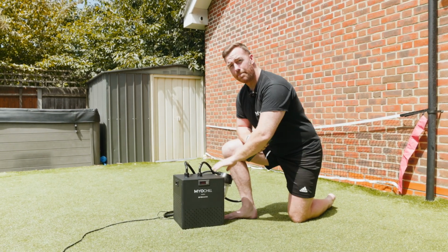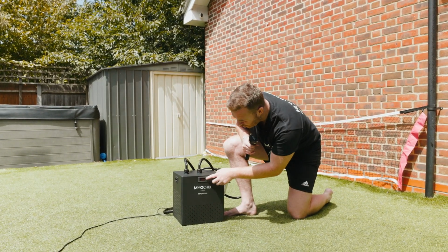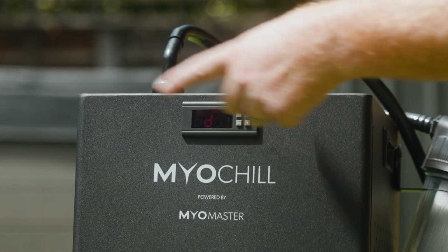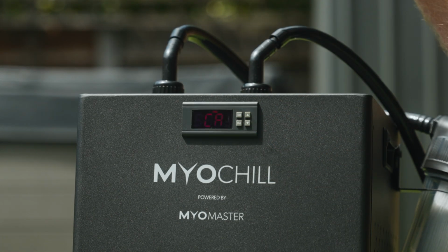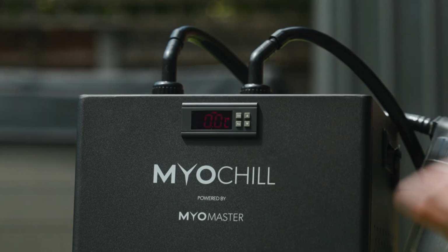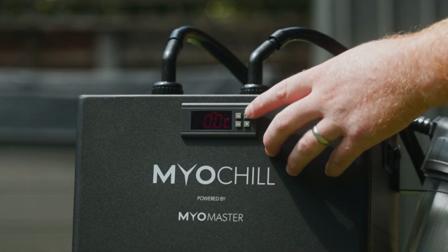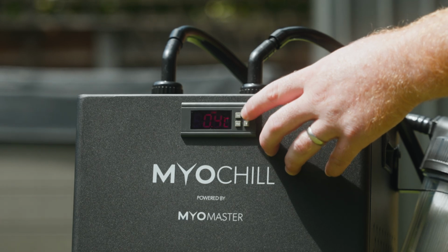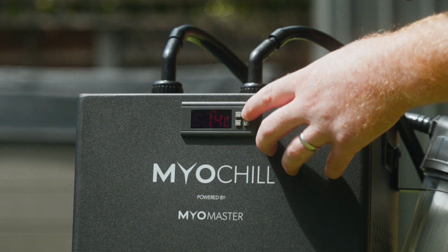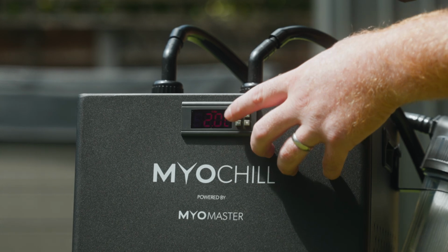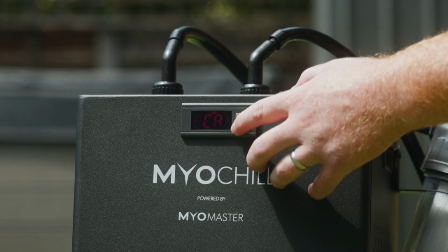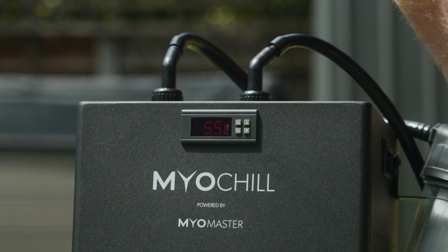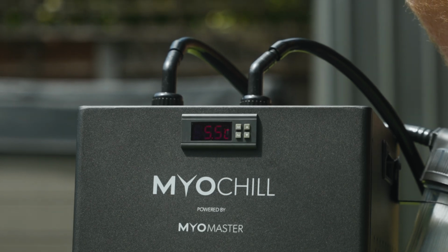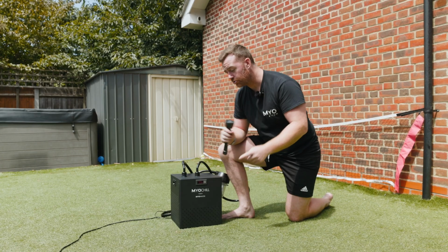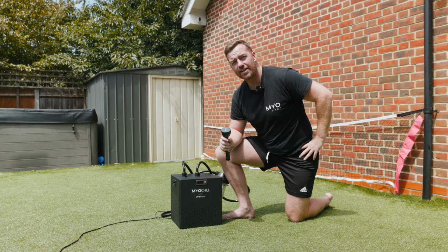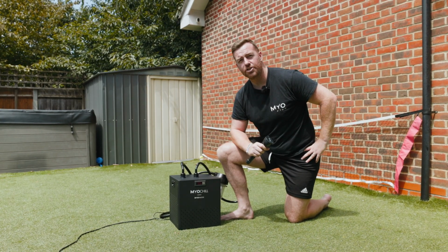To change this, we're going to the back end of the chiller, and how we do that is we hold the set button for 3 seconds, it will bring up a D, and we go down to CA. We then press the set button again, and as you can see, it's got 0 because they should be matched. But actually the chiller is 2 degrees less, so we want to do a +2 to change that up to the required temperature. We press set and we press reset, and as you can see, it is now 5.5 degrees, the same as our thermometer. You do the same in reverse. So if it was the other way round, you go -2 to get it to the correct temperature so it marries up with your water temperature.